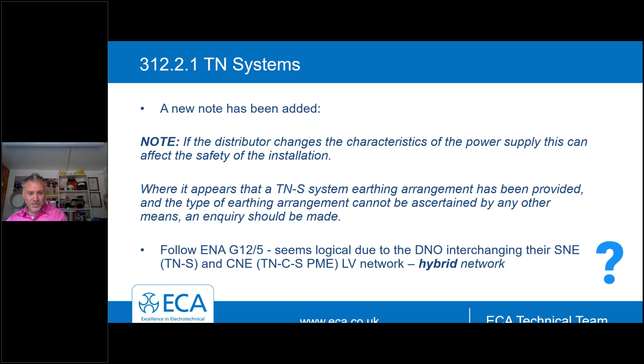Something new, or is it? A new reference to protective neutral bonding, PNB. This is a variation of TN-C-S, but it's not PME. PME is protective multiple earthing, where there's a source electrode and additional electrodes at regular points, whereas PNB is a single point earthing of the source, where only one connection at one point has been made.